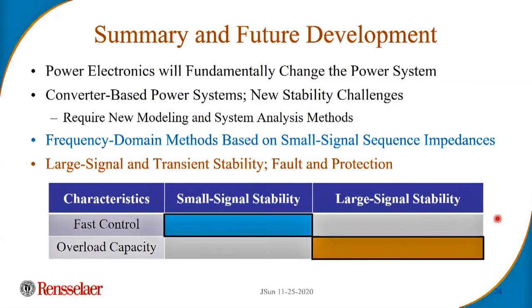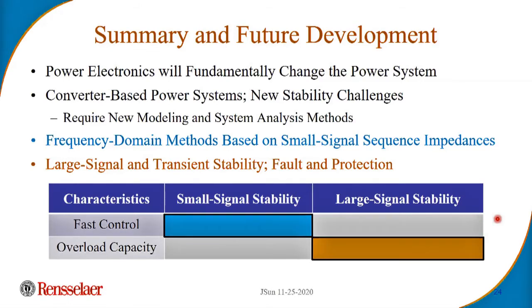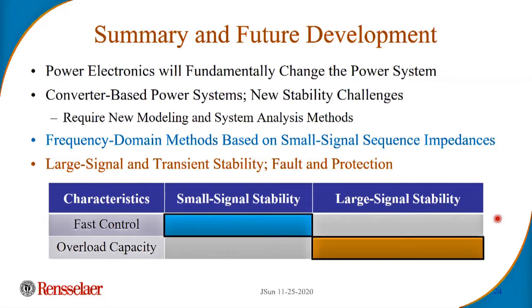Dylan, I want to reflect on one other thing that Jan talked about, which he mentioned and then moved past. That's the whole question of fault management. It seems to me there's a real sleeper here, in the sense that we have a whole power system and a whole fault sequencing, prioritization and management process built on this inherent overcurrent capacity to trip the events. I've raised with the power utilities a number of times: what are you going to do with converters? You should be thinking about how to rebuild your fault management process, the whole sequencing process. And they look at me in horror and say, you can't do that. Where do you think that's going?